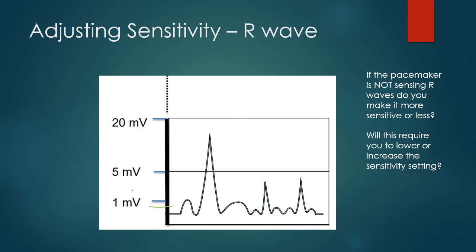Now that you're dialed in for P wave sensitivity, how do we know the machine won't get triggered by the R wave or T wave? In a dual setting where we're sensing both A and V, we know there should be an R wave following within less than 0.2 seconds — the PR interval. If there's no R wave within 0.2 seconds, it's time for the pacemaker to act. Since we're pacing both V and A, there are wires going to both chambers.